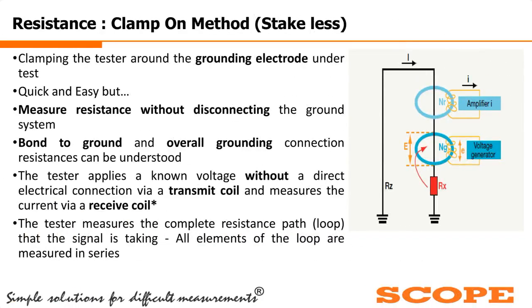So first we will see the clamp-on or stakeless measurement method. This is a quick and easy way to measure the grounding resistance, but there are some limitations of this method. First we will see how this measurement takes place. In this measurement, we apply a known voltage of a certain frequency into the grounding connection via a transmitter coil or a voltage generator, and the leakage current is measured through a receiver coil, a separate coil used for the measurement of leakage current. Based on these two values, voltage and current, the earthing resistance is calculated.